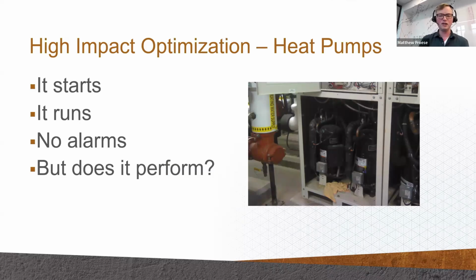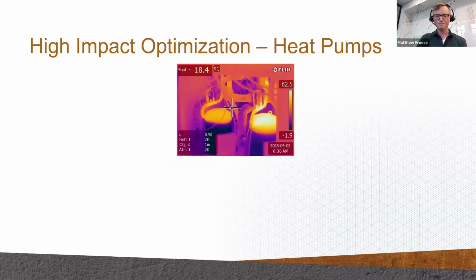Yeah, and then getting into the last bit here, just on heat pumps. This is a real unit. We worked with a geothermal heat pump that had been in operation for a while. We got there and noticed there was something going on. Both compressors in this unit here at the end were running. They started when called, and there weren't any alarms, but when one of the compressors ran or said it was running, there was no change in temperature in the system at all. Nothing seemed to happen. So we went out to take a look at it in person. You got to go see what's going on in the real world.